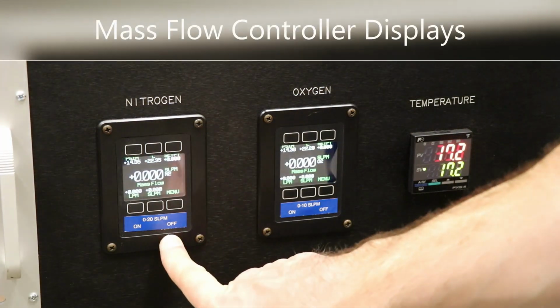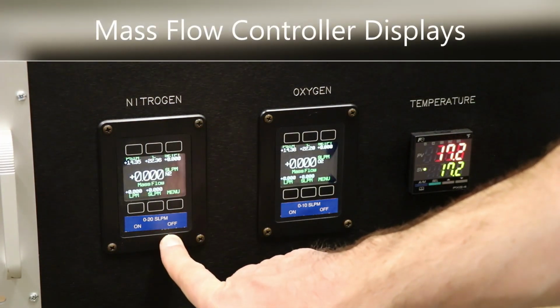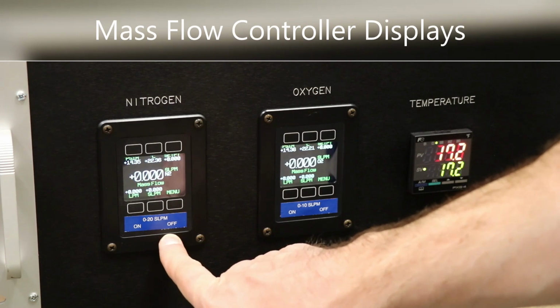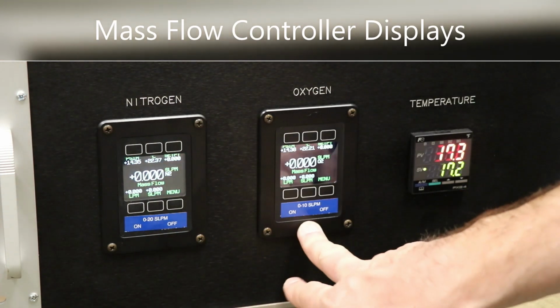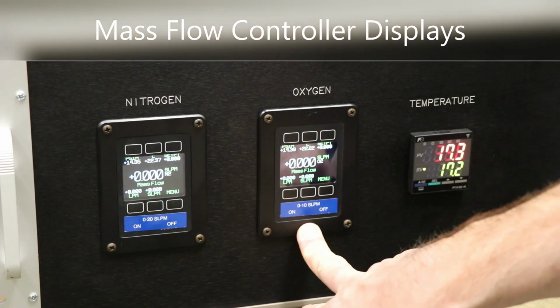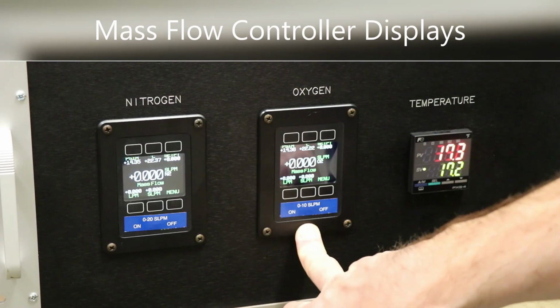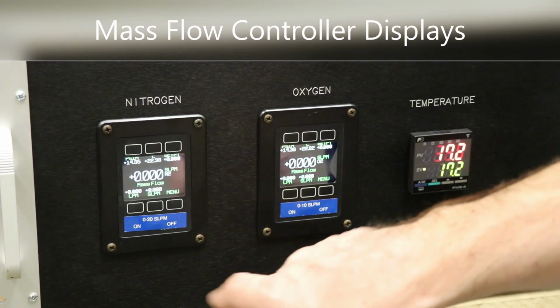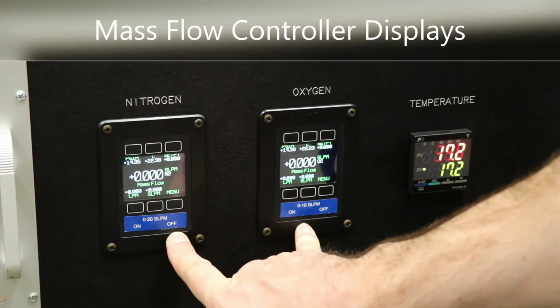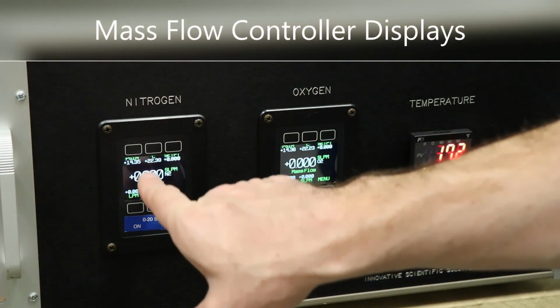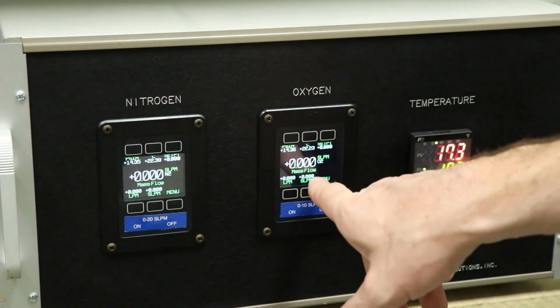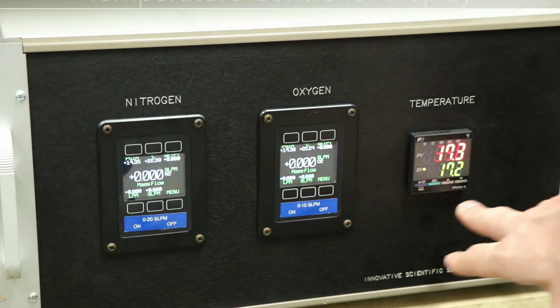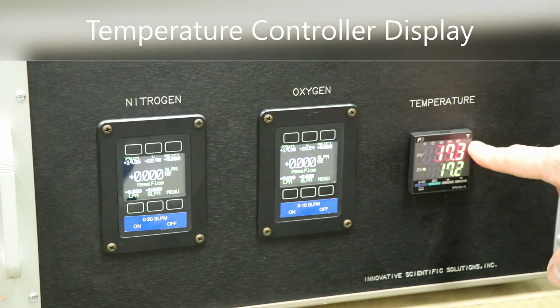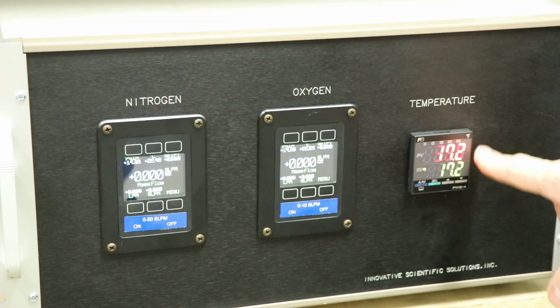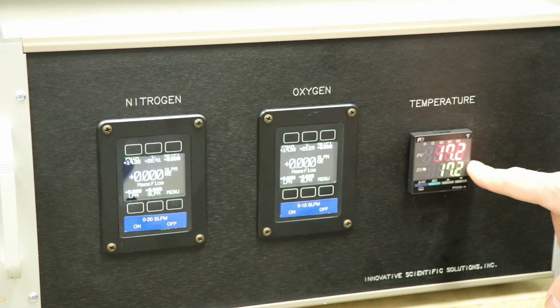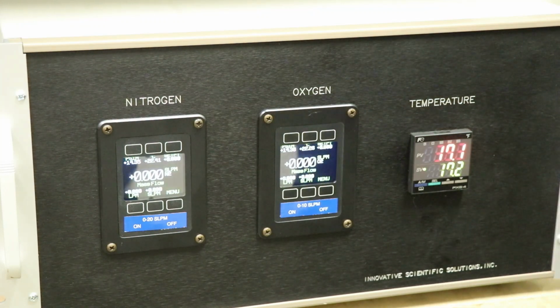The nitrogen mass flow is set by the program from 0 to 10 standard liters per minute, and has a range of 0 to 20 standard liters per minute. And the oxygen is variable based on the set pressure. The range of the flow controller is 0 to 10 standard liters per minute. So when the gas is flowing through the system, when you reach a set point, you will see this number go to 10 standard liters per minute and this number change based on the pressure setting. For the temperature, this is the current temperature of the heatsink in the cell, and this is the set point temperature that is given by the program.